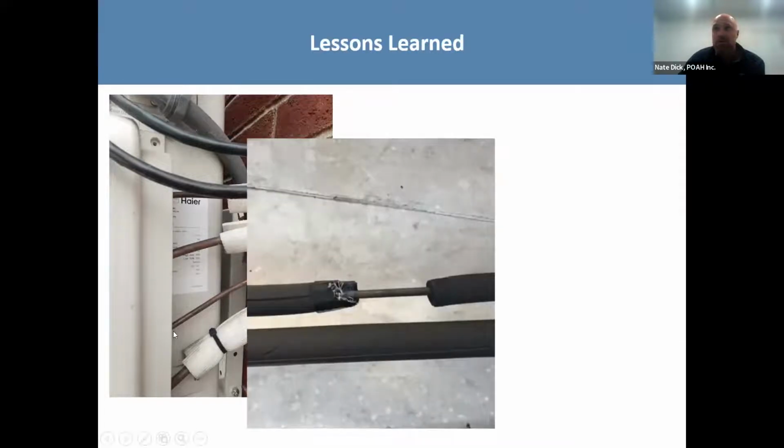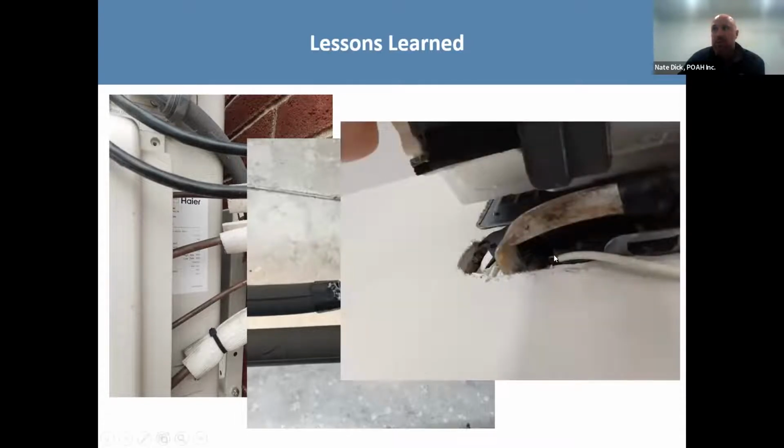Same thing with this next image. This was from a roof in Chicago, where this was pretty evident that we didn't get the product we had hoped for. The other thing that we've run into at some sites is the condensate hose on this terminal unit in the living room is obviously kinked. So that condensate not being able to drain properly, that can cause a lot of problems. So proper installation is critical, especially on those condensate lines. No kinks. You don't want to see that.